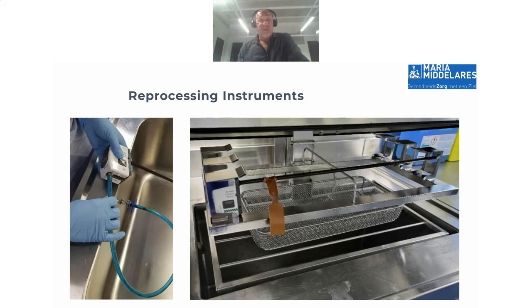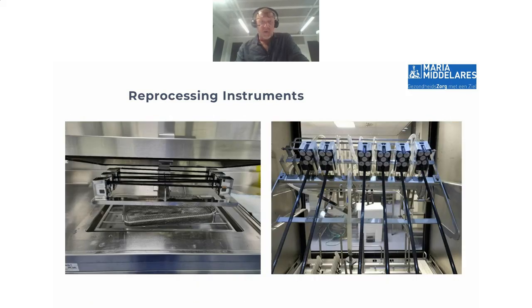When it comes to CSSD, we flush manually the two ports of each instrument, and then the robotic arm goes for about half an hour in our ultrasonic device. On the left, you can see our ultrasonic device. On the right, there's a rack to put our robotic arms on it, and it goes for about 1.5 hours in our washer disinfector.